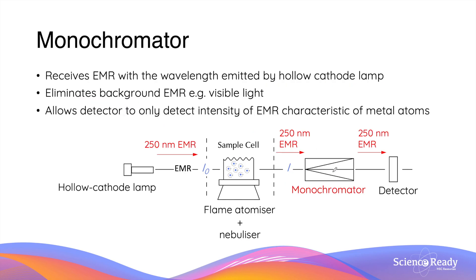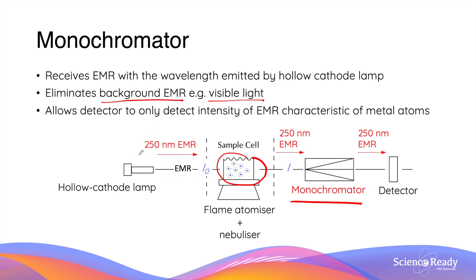The EMR that exits the flame is passed through a monochromator. The monochromator's job is to receive EMR with the wavelength characteristic of the metal being analysed while eliminating every other source of EMR, including background EMR such as visible light. By eliminating unwanted sources of EMR, we allow the detector behind the monochromator to analyse the intensity of the characteristic wavelength belonging to the metal atom. For example, if we are analysing a metal species that absorbs EMR at 250 nm, the hollow cathode lamp produces 250 nm EMR, which passes through the flame where some is absorbed, reducing its intensity. The monochromator then filters all radiation except the 250 nm radiation, allowing the detector to measure the intensity of this particular radiation.